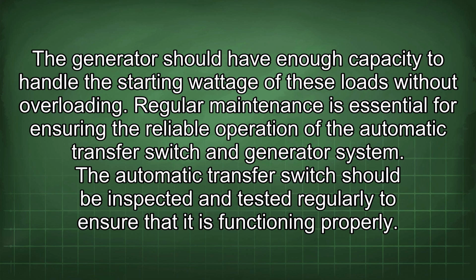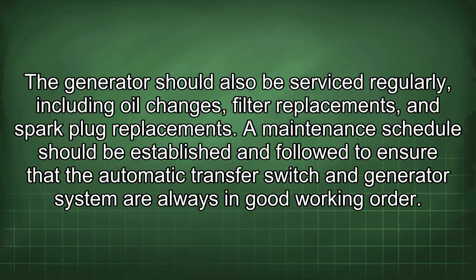Regular maintenance is essential for ensuring the reliable operation of the automatic transfer switch and generator system. The automatic transfer switch should be inspected and tested regularly to ensure that it is functioning properly. The generator should also be serviced regularly, including oil changes, filter replacements, and spark plug replacement. A maintenance schedule should be established and followed to ensure that the automatic transfer switch and generator system are always in good working order.